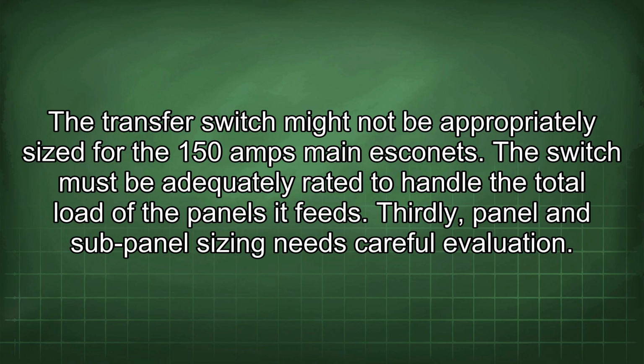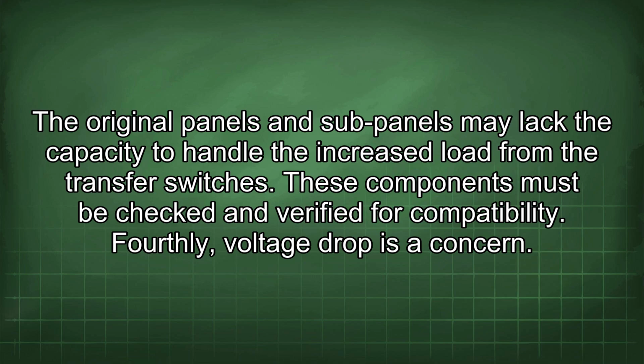Thirdly, panel and sub-panel sizing needs careful evaluation. The original panels and sub-panels may lack the capacity to handle the increased load from the transfer switches. These components must be checked and verified for compatibility.